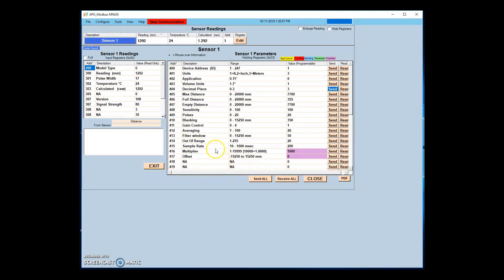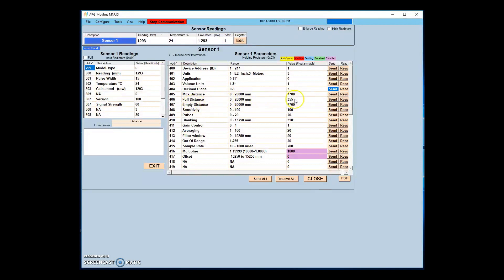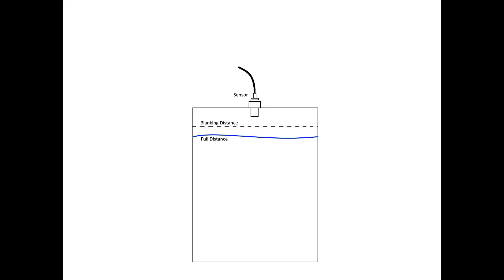The full and empty distance parameters are designed for monitoring tank levels and set the distances from the sensor zero point that the vessel is considered full or empty. The full distance parameter must be set to a distance from the zero point that is equal to or greater than the blanking distance. The empty distance must be less than the max distance for the sensor to accept readings when the vessel is empty.